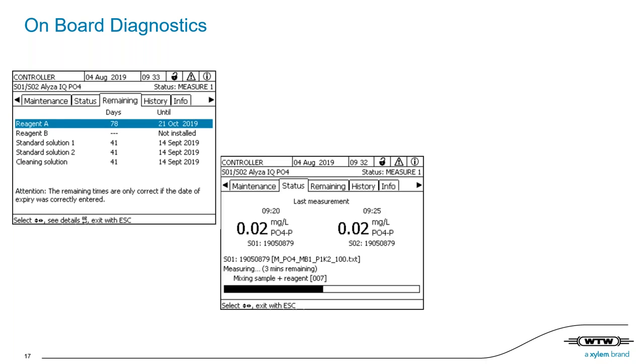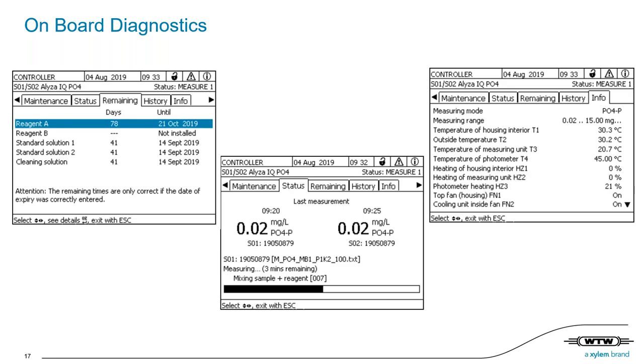You can also see the last measurements and the current process stage of the next measurement. In this example, the Alyza is in the mixing stage of the measurement, and it will be approximately 3 minutes until the measurement is completed and the reading is updated. In addition, it is displayed during waiting mode when the next process stage will take place. For full transparency, a detailed overview is provided for temperatures and system status within the info screen. As I mentioned, we have 3 different temperature compartments for a complete optimization of the chemical reaction and the detection, and thus the reliable measurement. And all these compartments are controlled for the temperature, and here you see it completely transparent.